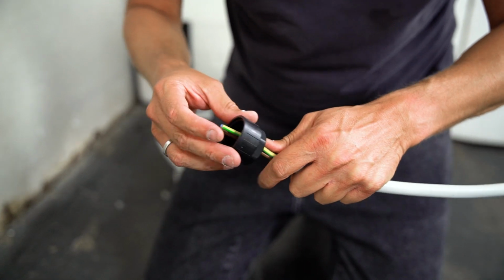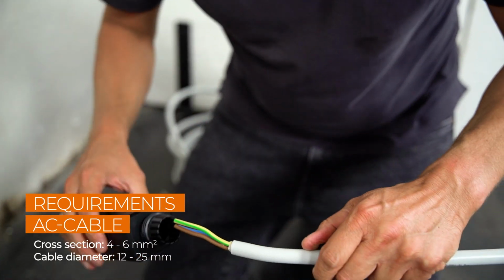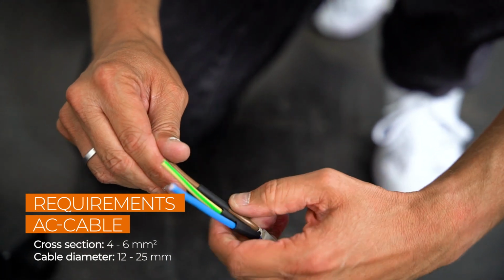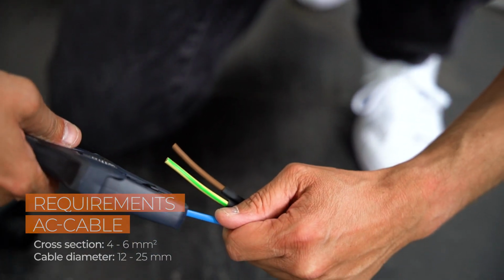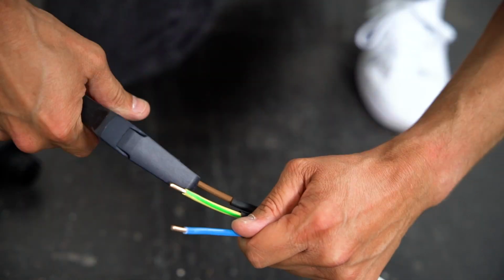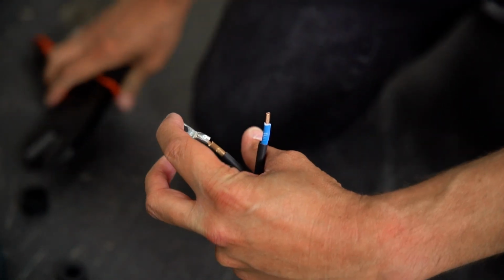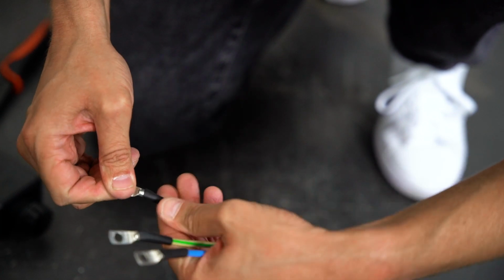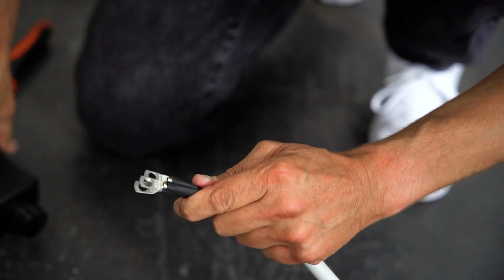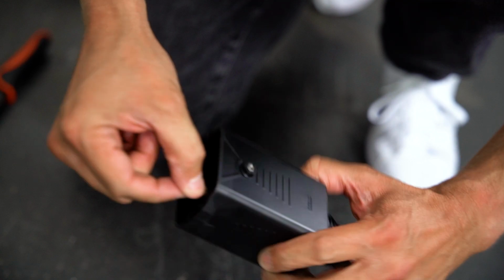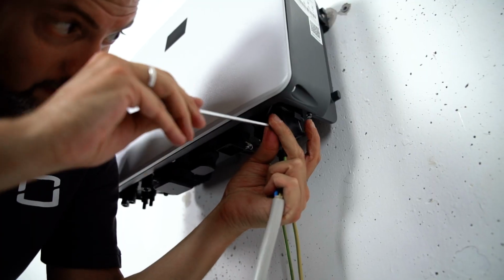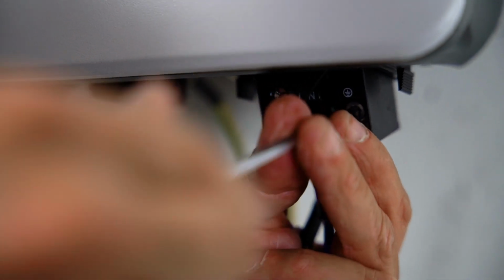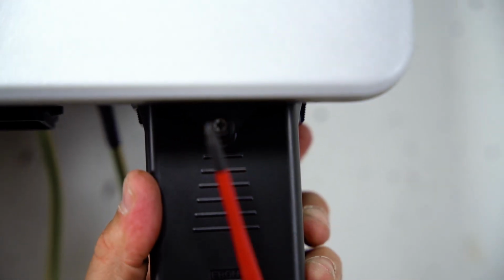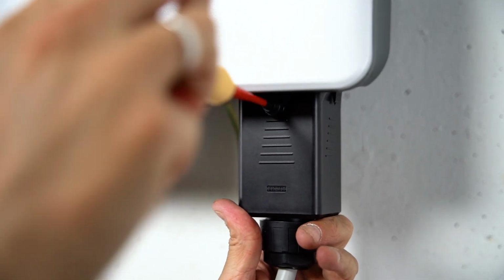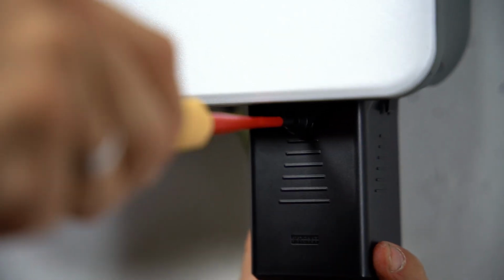Now let's connect the AC plug. Remove approximately 4 to 5 cm of the cable sheath of the AC cable. Then, strip approximately 2 to 3 mm of the inner cables. Add cable terminals and heat shrinks to the AC cables. Because of our handy plugs, you don't have to open the inverter for installation. Simply pull the cables through the individual components of the plug and fix them with the included screws. Push the connector until you hear a click and fix it with an M4 screw. Last but not least, you have to tighten the fasteners.